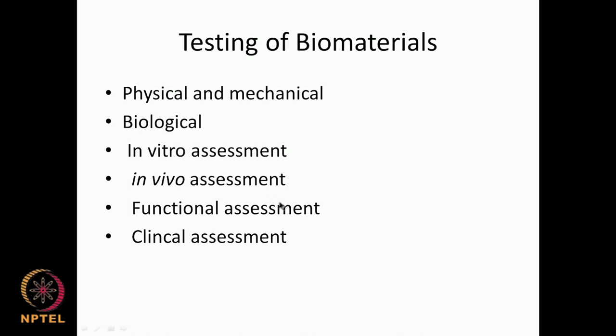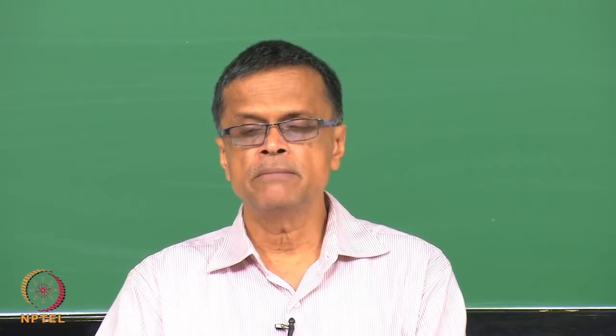Functional assessment is also required — for an artificial valve that must open and close 100,000 times, we test whether it actually works. Then comes clinical assessment where clinicians examine it and test on volunteer patients to see whether the biomaterial performs its duty. A lot of testing — physical, mechanical, biological, in vitro, in vivo, and clinical — must be done before introducing the product to the market, almost like drug testing, with the process taking several years.